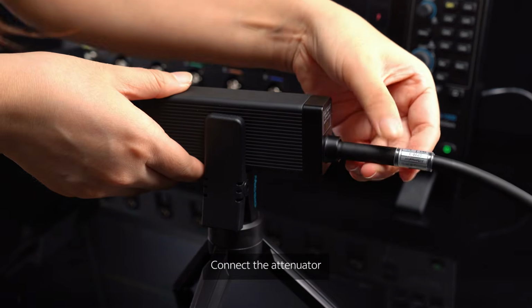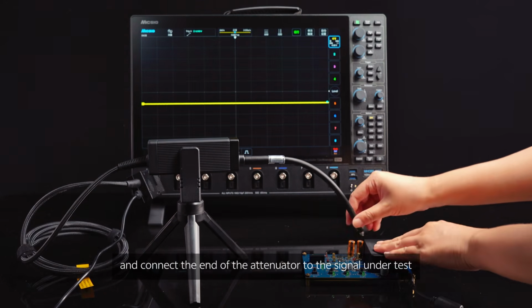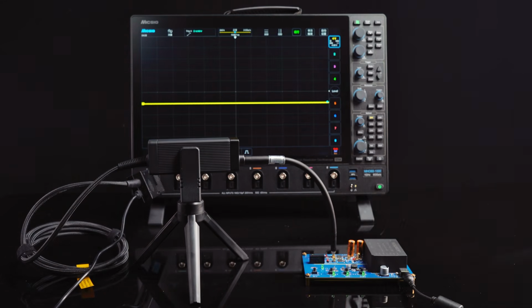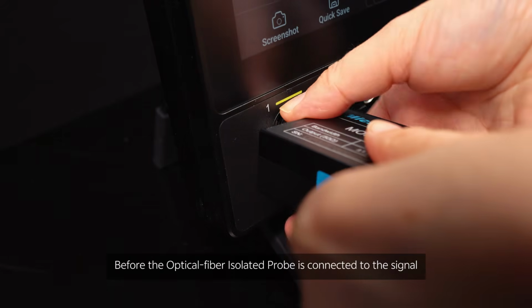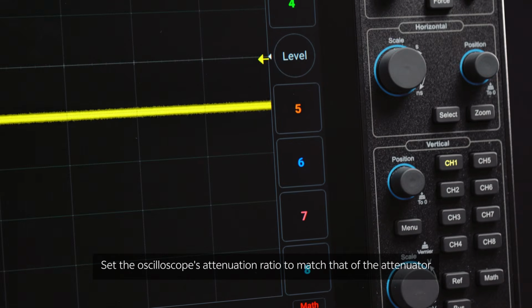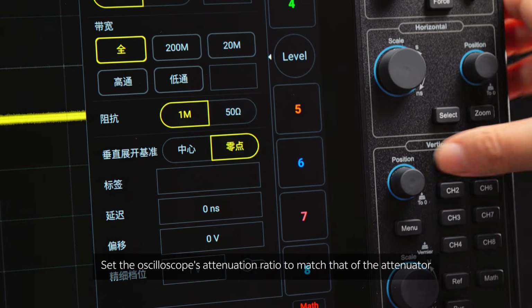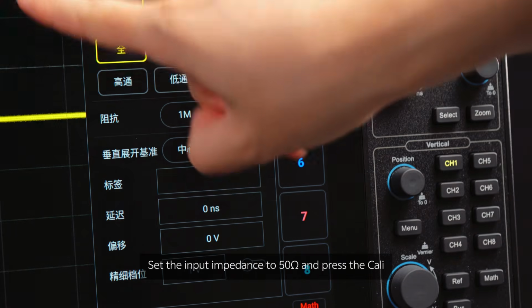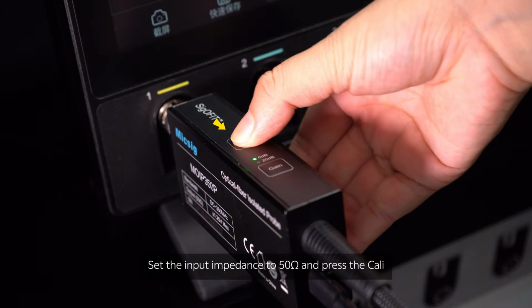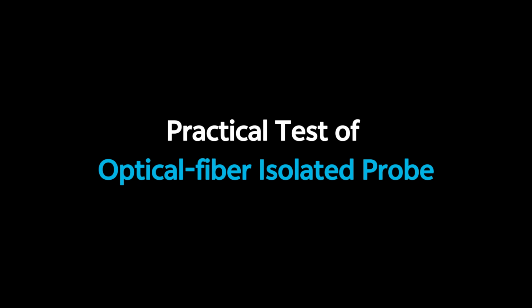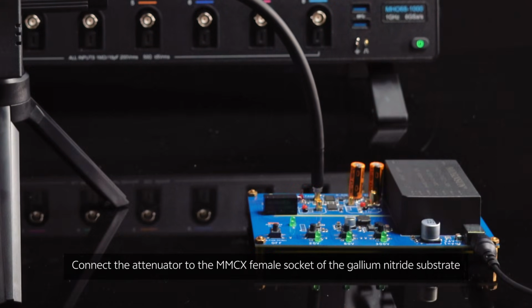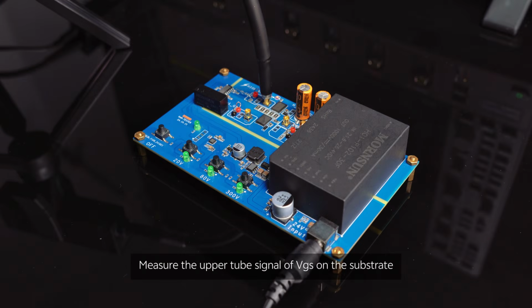Connect the attenuator and connect the end of the attenuator to the signal under test. Before the optical isolation probe is connected to the signal, set the oscilloscope's attenuation ratio to match that of the attenuator. Set the input impedance to 50 ohms and press the Cali. Connect the attenuator to the MMCX female socket of the gallium nitride substrate. Measure the upper tube signal of VGS on the substrate.